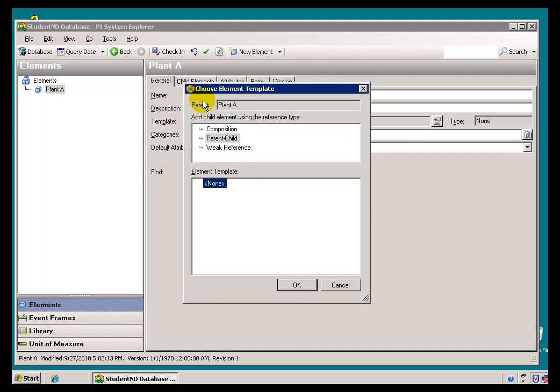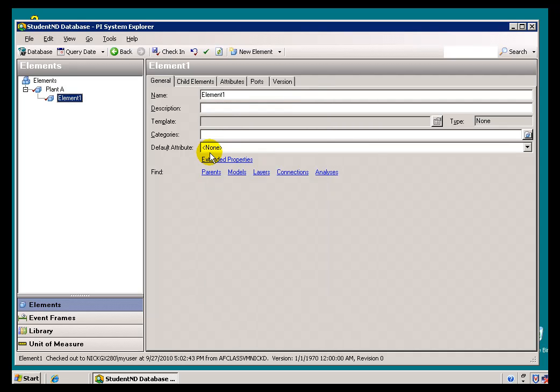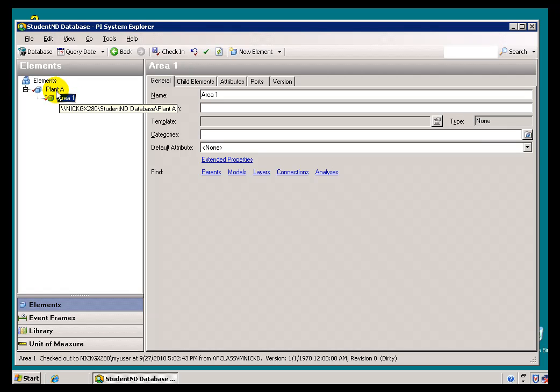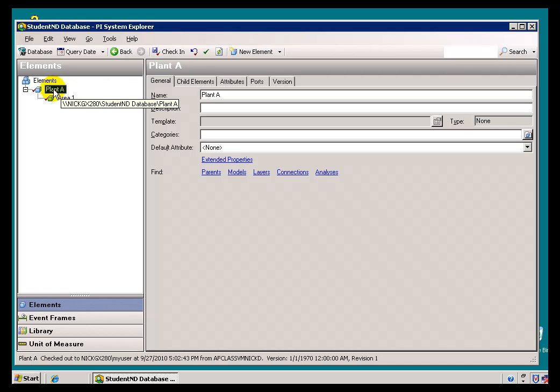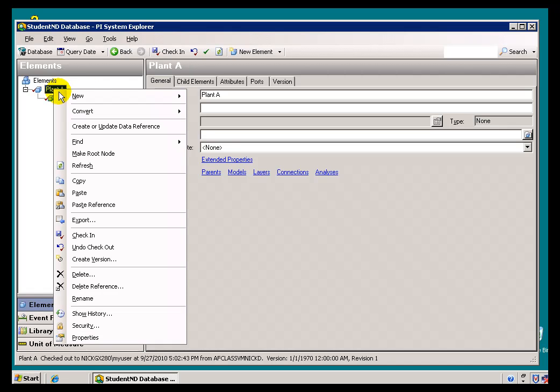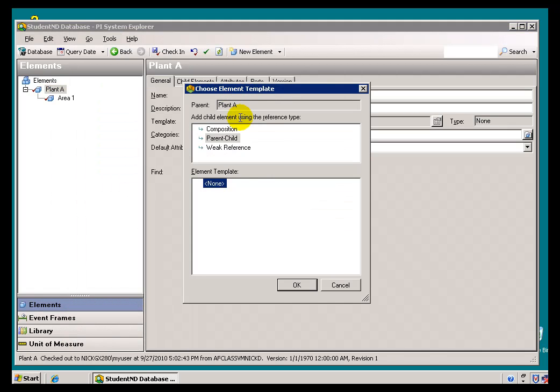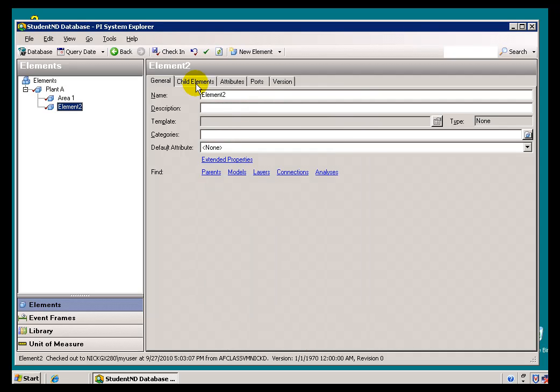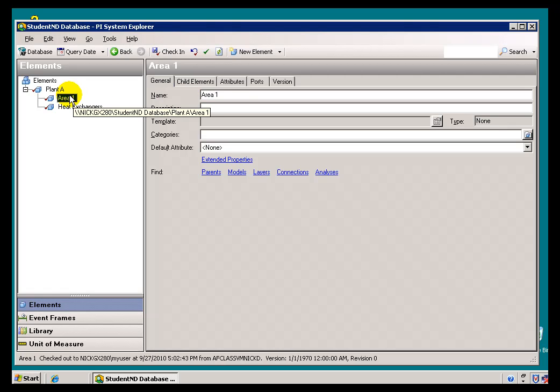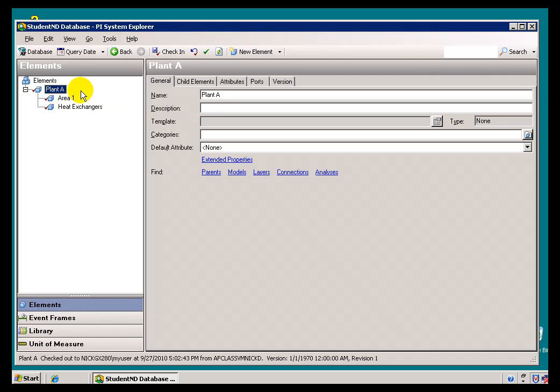I can check that in, and that stores that. Now, an alternate way to do this is to right mouse click on a specific Element and choose New Child Element. That will create a Child underneath that Element. If I chose Element, it would be on the same level as the Element that is selected. I'll choose a New Child Element. This is where we now get that choice of Composition, the Parent Child which is Strong, or the Weak Reference. I'm going to choose Parent Child. That's the default. In this case, let's build two of them. We'll do Area 1 and Heat Exchangers, as we described. Let's do another Child Element. We're going to call this Heat Exchangers. Once these look the way we want them, we'll go ahead and check those in. That commits them to save them to the AF database.